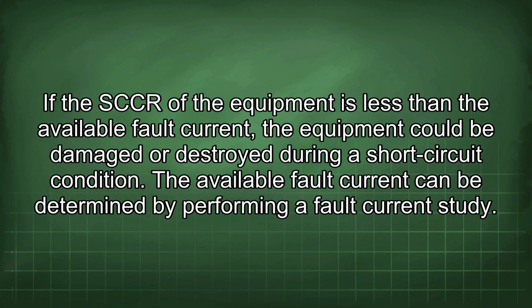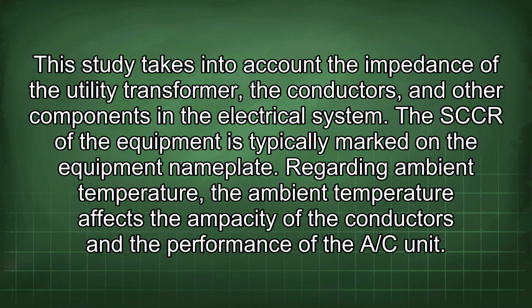The available fault current can be determined by performing a fault current study. This study takes into account the impedance of the utility transformer, the conductors, and other components in the electrical system. The SCCR of the equipment is typically marked on the equipment nameplate.